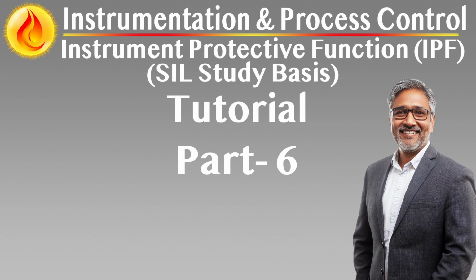Compensating measures during override period. To preserve overall risk tolerability while an IPF is disabled, one or more of the following must be implemented: increased operator surveillance or field monitoring, temporary activation of alternative protection measures, e.g. alarms with manual response, reduced process throughput or derated operations, administrative controls and heightened readiness to respond to deviations.